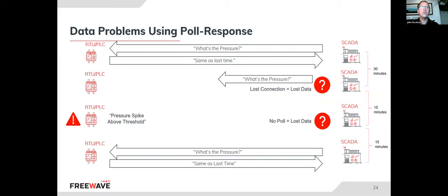How did we do that with Freewave Edge? Here are some data challenges you might have with an over-the-air centralized poll-and-response system. We've got PLCs and field devices on the left and the SCADA system on the right. The SCADA system keeps asking, what's the pressure? And the PLC reports back the same as last time. Say we're updating every 30 minutes: if the SCADA system polls and there's no connection, there's no response, which means lost data.